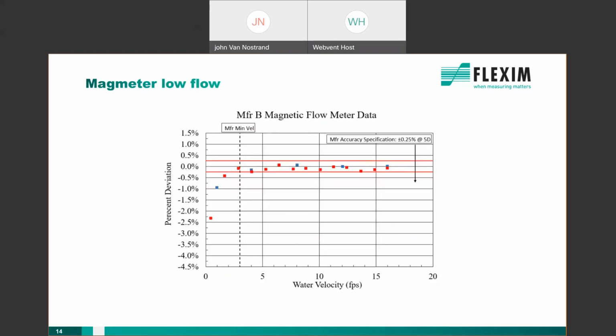Because of the voltage that's created as the media passes through the magnetic field, the velocity of the media becomes very important, which is often why they put a reduced bore in the magmeter, because we want to increase that velocity. So the sweet spot for a magmeter is from 3 to 33 feet per second. But if you take a look below 3 feet per second, you can see the meter will still read. However, the accuracy does drop off. It becomes like a bell curve, and the lower you get below that sweet spot, the more inaccurate the meter can become. So this illustration shows a meter that was tested at the University of Utah.